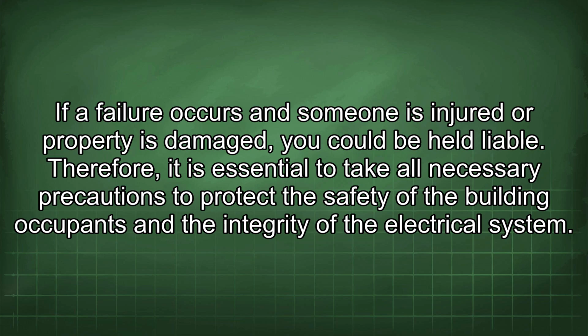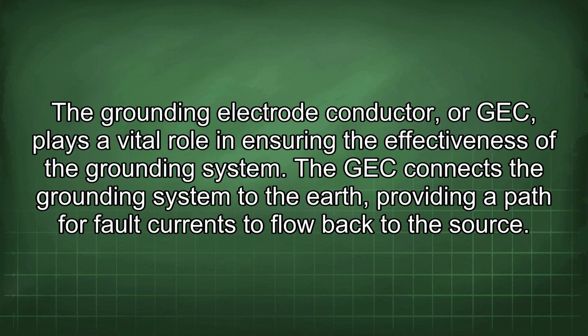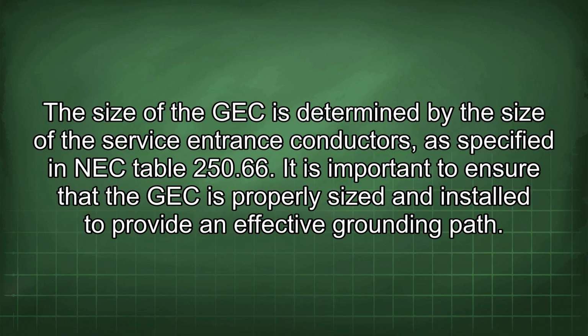of the electrical system. The grounding electrode conductor, or GEC, plays a vital role in ensuring the effectiveness of the grounding system. The GEC connects the grounding system to the earth, providing a path for fault currents to flow back to the source. The size of the GEC is determined by the size of the service entrance conductors, as specified in NEC Table 250.66. It is important to ensure that the GEC is properly sized and installed to provide an effective grounding path.